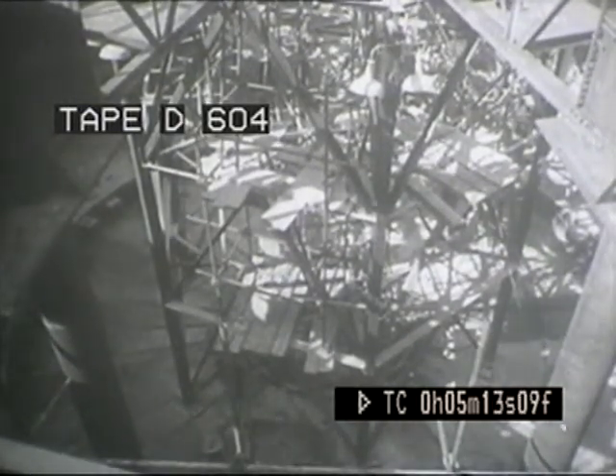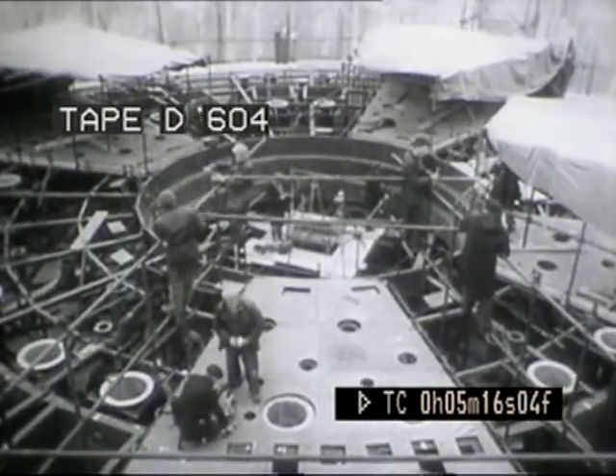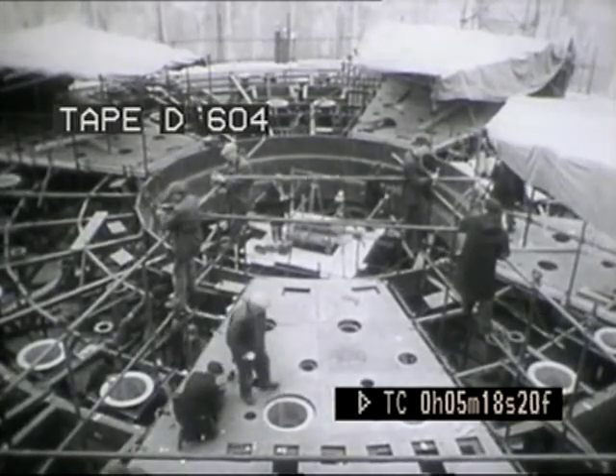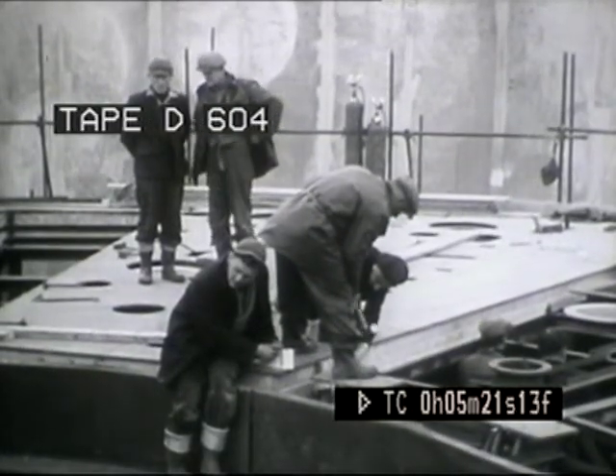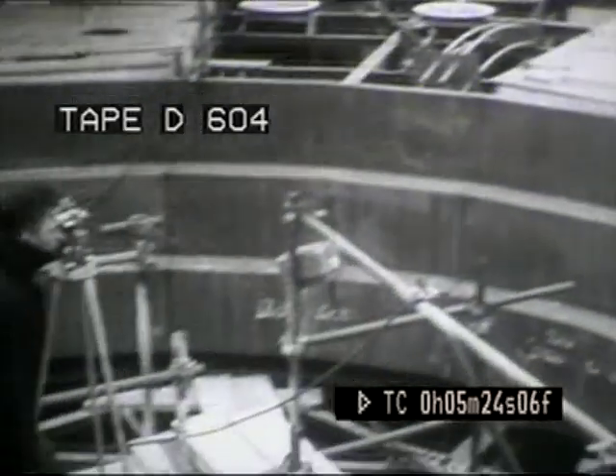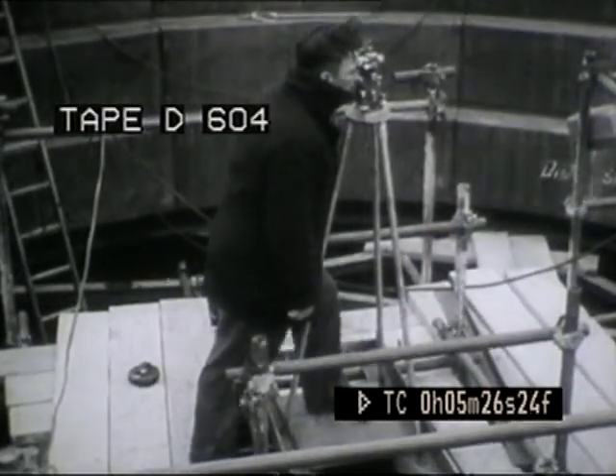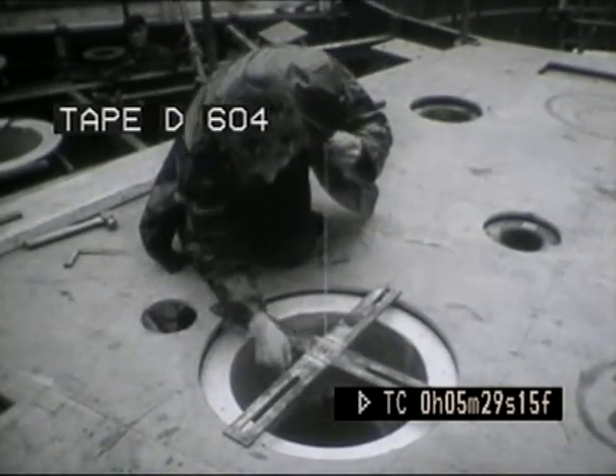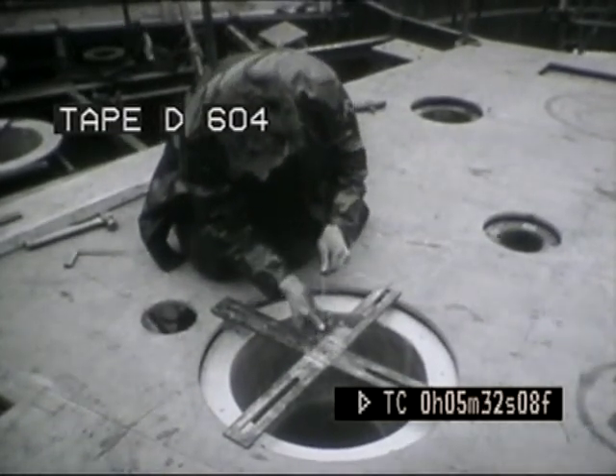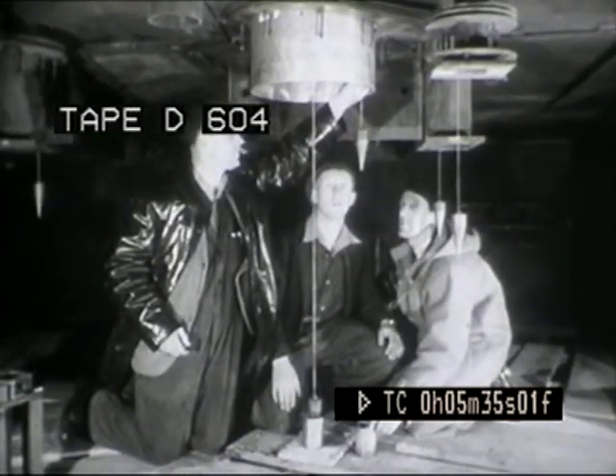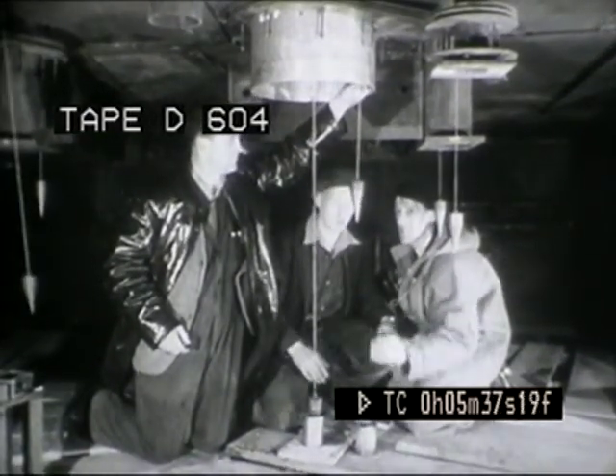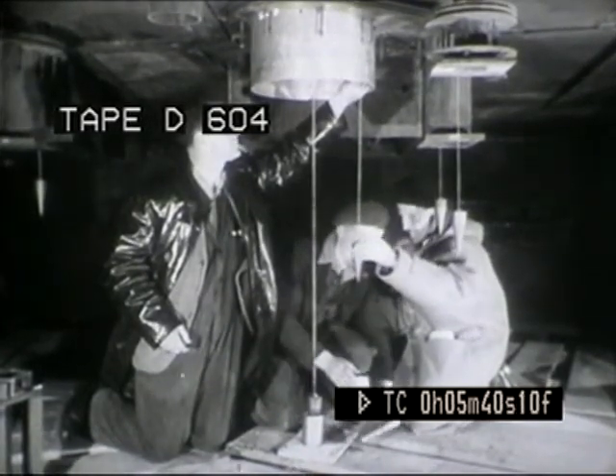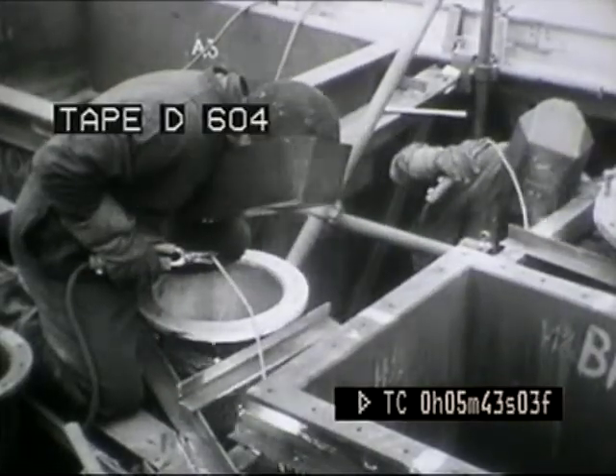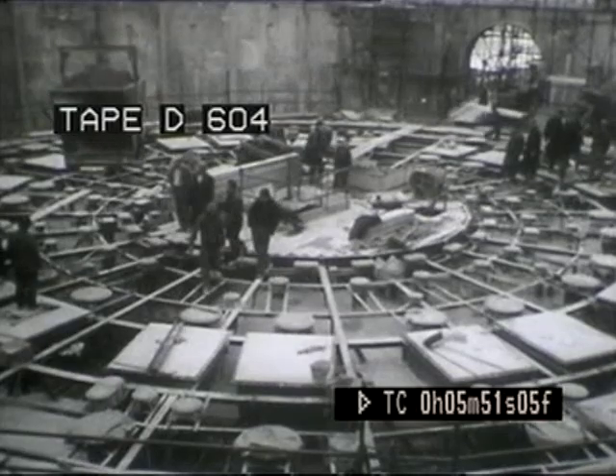Over 200 openings had to be left in the roof for equipment and fittings. To position the liners for these, wooden templates were laid on the steel reinforcing sections and lined up by theodolite. Plumb bobs dropped from the template above were used by the fitters below to line up the openings to the very close tolerance permitted. As soon as the liners had been set, they were welded to supporting struts on the steelwork. When this had been done to all the fittings, concrete pouring began.